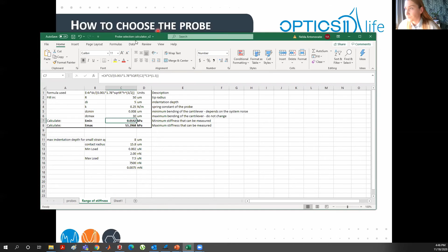you can choose the radius that you use, for example, 50 micrometers. This is the indentation depth that you would like to measure at, let's say 5 micrometers, and the probe stiffness, 0.25 Newton per meter. Then this is the minimum threshold, the minimum amount of cantilever bending that your system is able to resolve, which depends on the system noise level. The quieter the system, the lower this number can be. And this is the maximum bending of the cantilever, so we recommend a maximum of 30 micrometers. What you get as a result when you fill in all these details is the minimum Young's modulus that you can measure and the maximum Young's modulus that you can measure.